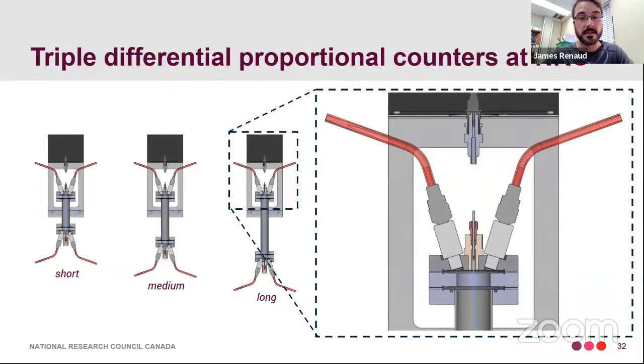So the three activity concentrations are obtained by subtracting pairs of activities measured by each counter, divided by the difference in their volume. And the volumes are calibrated before the units are put together. That's done here at the NRC by a different group. They specialize in volume measurements, among many other things, but what they do is essentially measure the amount of water that it takes to fill one of these wire chambers to determine the volume with a very high relative accuracy.